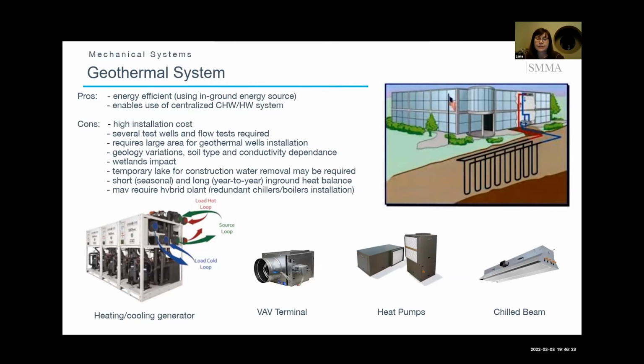There is a lot of drilling for the wells. This size of school could involve maybe 300 wells to be drilled. Before we decide how to proceed with the system, we have to do a few test wells, and sometimes test wells do not produce the desired results, so we have to move and try another one. Along with the test well, we have to do a flow test for each well, for each location, and the price could be very high for these test wells. It could start from 25,000 and go as high as 35,000 just to test it.